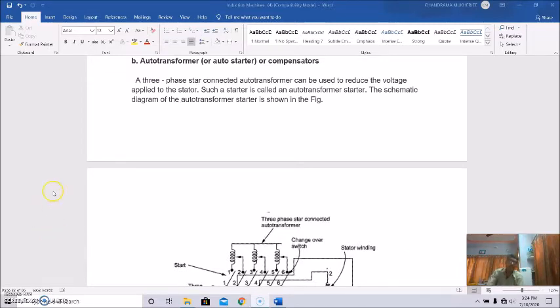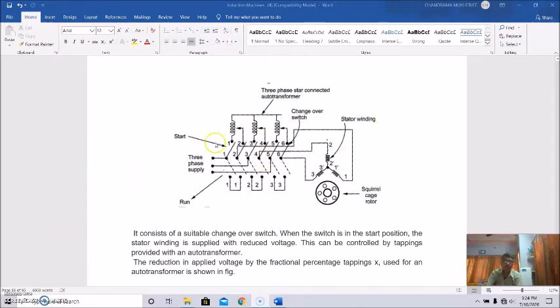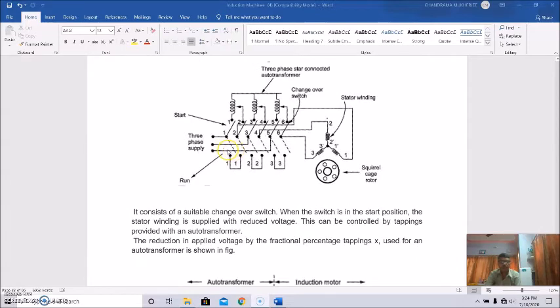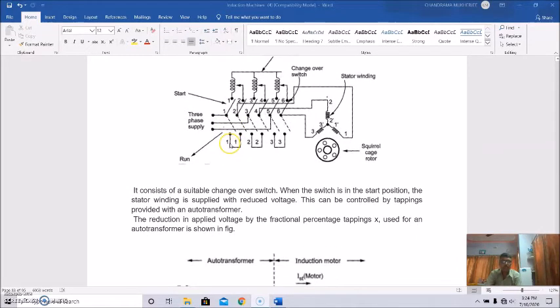The schematic diagram of the auto transformer starter is shown here. This is the three-phase star connected auto transformer. This is the double pole type switch. Here the three-phase supply is given. This is the stator winding and this is the rotor. This switch is called a changeover switch. At starting it will be connected to the auto transformer, and in running condition it will be changed over to this terminal so that the full voltage can be placed across the stator terminals.